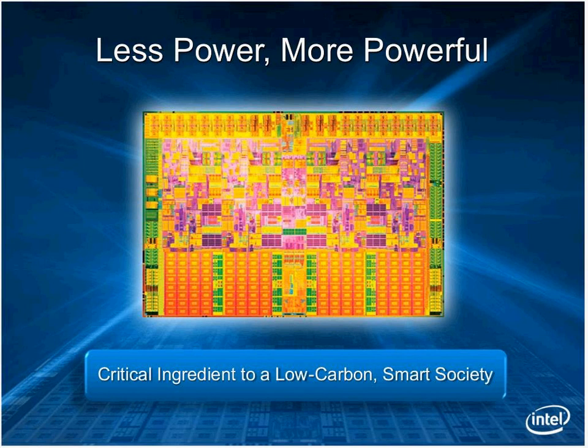One of the things that's changed there, though, is we've really forced a tighter collaboration between facilities and IT because we've increased the densities of the computing gear pretty significantly. It used to be that you needed 5 kilowatts for a rack of computer gear. Now we have racks that could consume as much as 20 or 30 kilowatts, and you need a lot more planning associated with that kind of density. Now, the news is you're doing much more work. It's much more efficient, but it also means that there has to be a much tighter integration between the IT people and the facilities people.